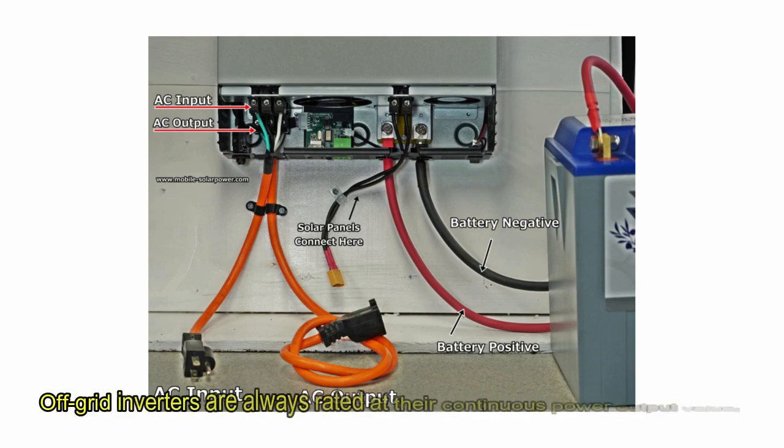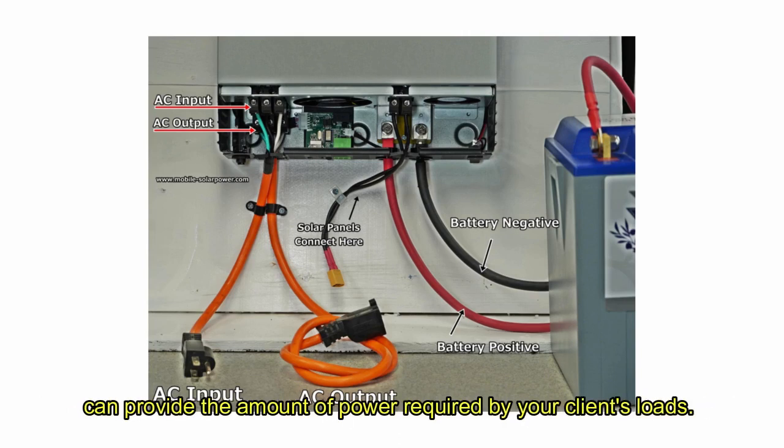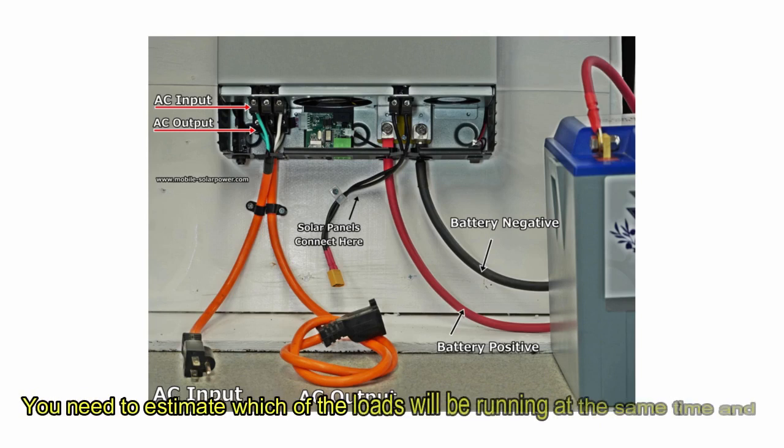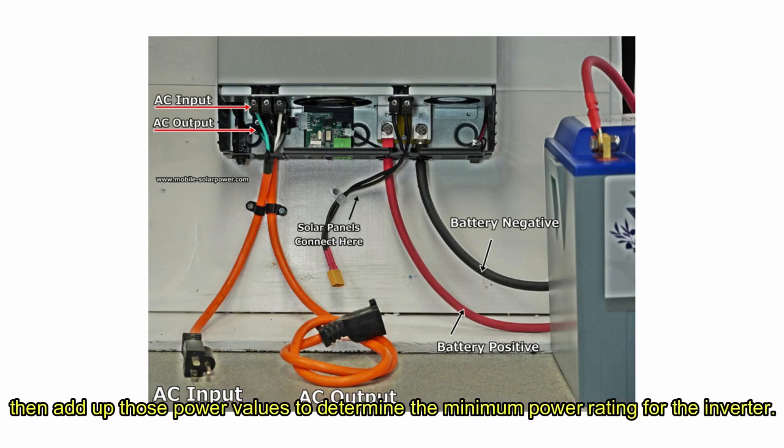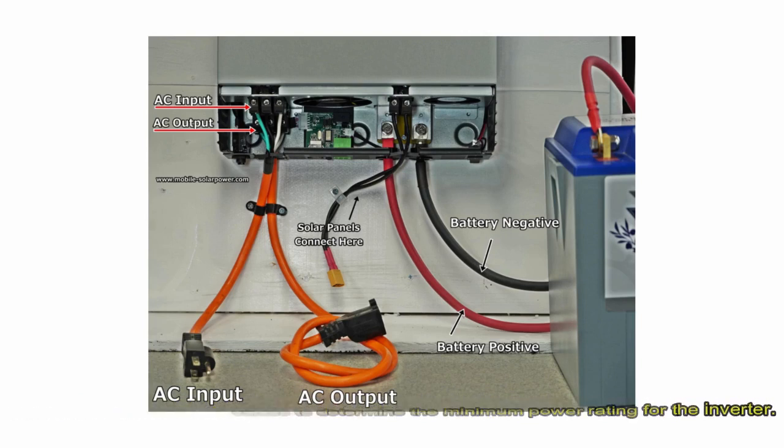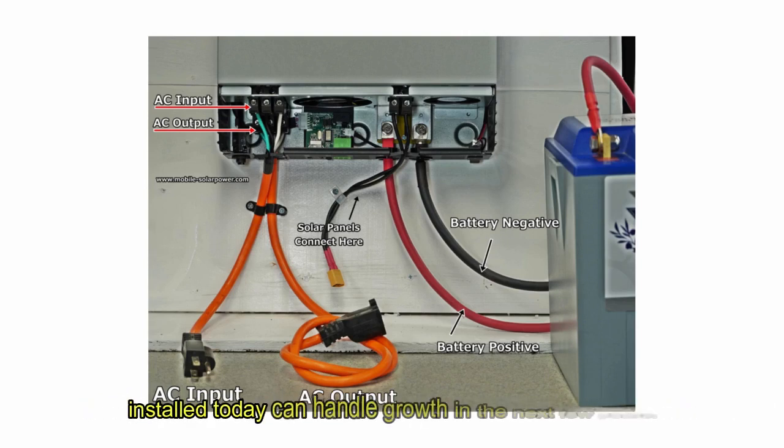Off-grid solar inverters are always rated at their continuous power out value, which means you need to make sure that the inverters you select can provide the amount of power required by your client's loads. You need to estimate which of the loads will be running at the same time and then add up those power values to determine the minimum power rating for the inverter. Consider future loads that may require power, so that the inverter installed today can handle growth in the next few years.